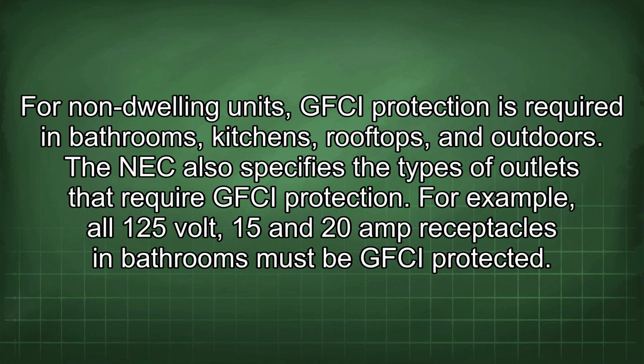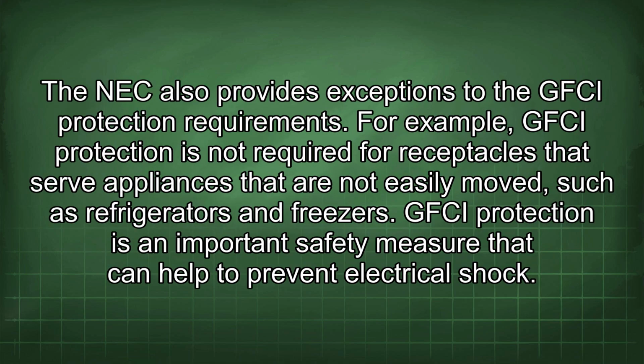The NEC also specifies the types of outlets that require GFCI protection. For example, all 125-volt, 15 and 20 amp receptacles in bathrooms must be GFCI protected. The NEC also provides exceptions to the GFCI protection requirements. For example, GFCI protection is not required for receptacles that serve appliances that are not easily moved, such as refrigerators and freezers. GFCI protection is an important safety measure that can help to prevent electrical shock.